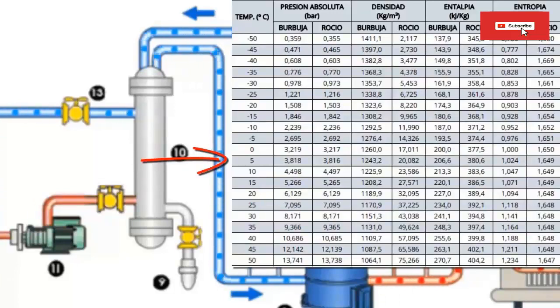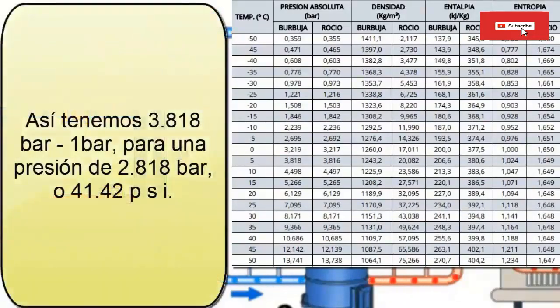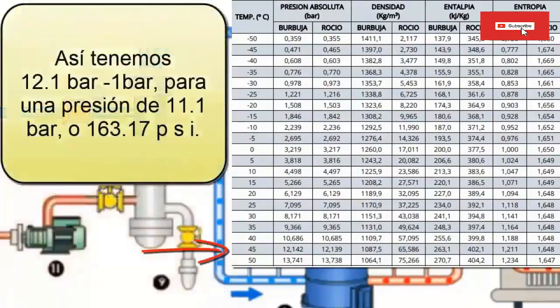We must subtract the atmospheric pressure from this value. In this way we find the pressure of the manometer. Thus we have 3.818 bar minus 1 bar for a pressure of 2.818 bar or 41.42 psi. For a system condensing temperature of 45 degrees Celsius, we can see from the table that the absolute pressure is 12.1 bar. We must subtract the atmospheric pressure from this value. In this way we find the pressure of the manometer.